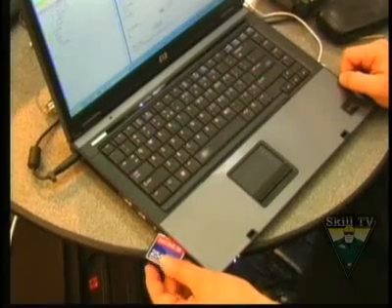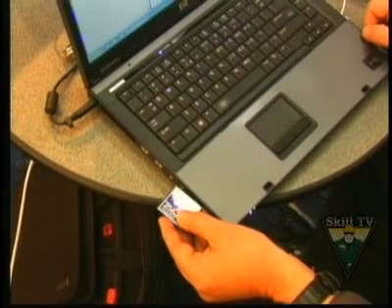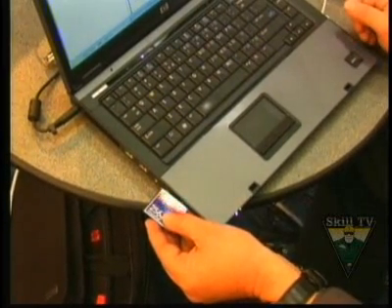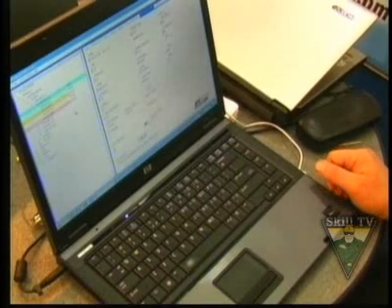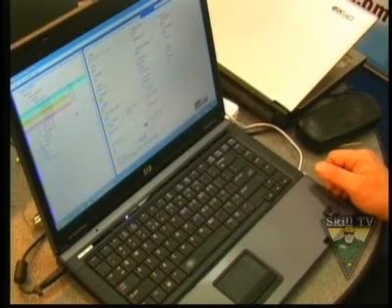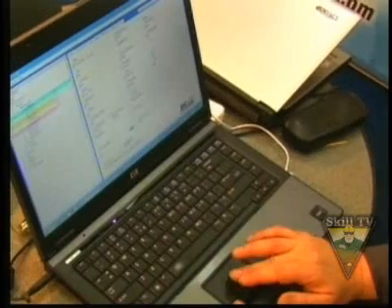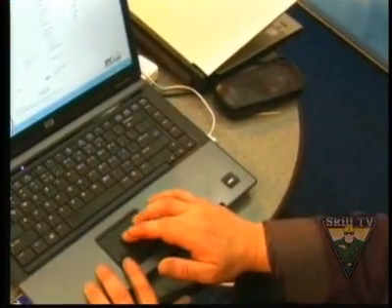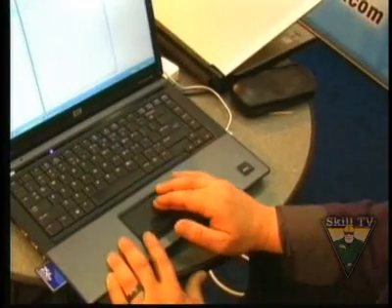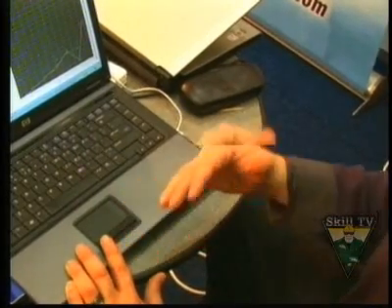I'm now going to take a minute and demonstrate. Once I've taken readings, I download them by simply taking a compact flash card, inserting it into my PCMCIA slot, and downloading my readings into the computer software. The software serves two purposes: it lets me take historical data — months of readings — and look at the history of a particular bearing, gearbox, or measurement point. That history is easily translated into a chart that lets us set alarm levels and look for anomalies or increases in decibel levels.